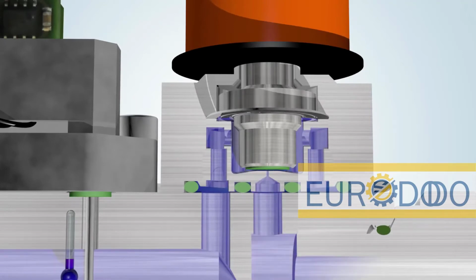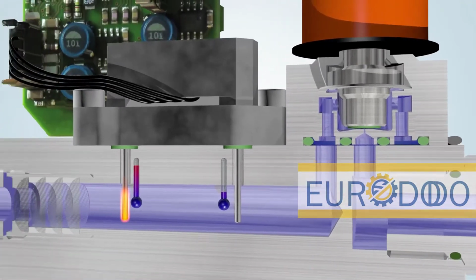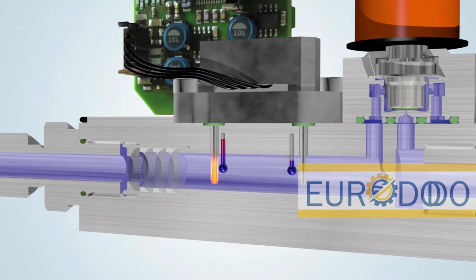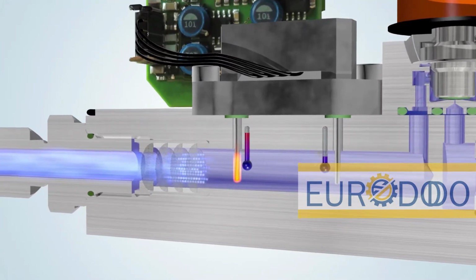The electromagnetic coil exerts a force on the magnetic plunger holder. This force is in balance with the linear spring that normally keeps the control valve closed. When the plunger comes free of the orifice, the result is a flow through the instrument.